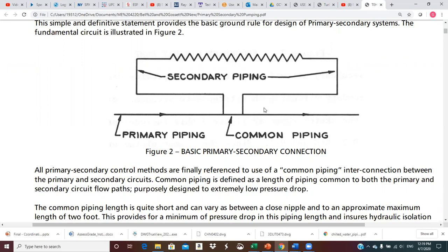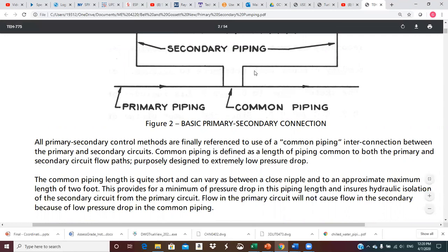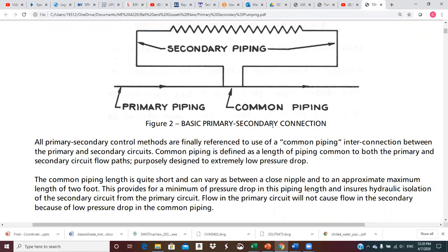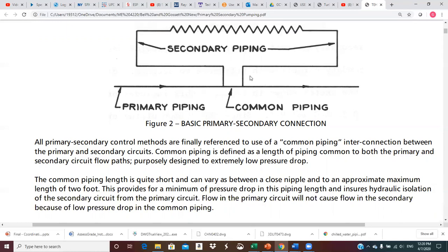This is the simplest arrangement and does get used sometimes, but generally speaking we'll have a supply and a return line. These connection points are very close together because we want hydraulic isolation between the primary pipe and the secondary piping. If these two lines are very close together and there is no pressure drop between these two points, then there's no pressure differential to force flow through the secondary. Having flow in the primary will not induce flow in the secondary — that's the term hydraulic isolation.